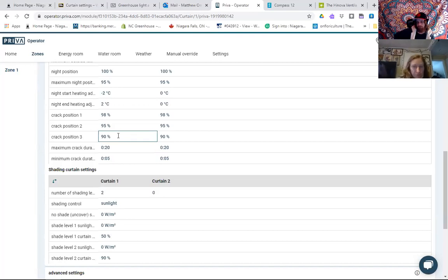Okay. If the temperature doesn't get up to where it needs to be at that point, then we need to look at, hey, what's going on with our boiler system? Is there something else going on that we need to figure out? Maybe our boilers aren't at capacity. Maybe there's something wrong with them. Our mixing valves aren't opening. Our pipe temperatures say that they're 90 degrees, but you feel them and they're really cold. So there might be something going on there, right? There might be something actually damaged that's not right. We have to figure something out there.